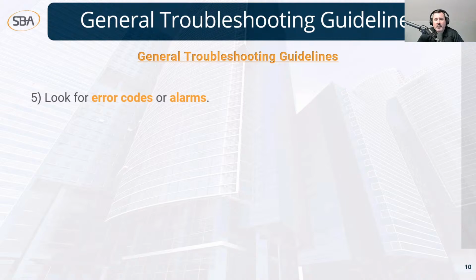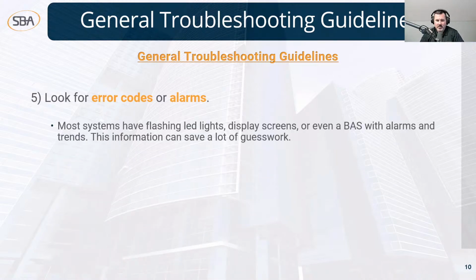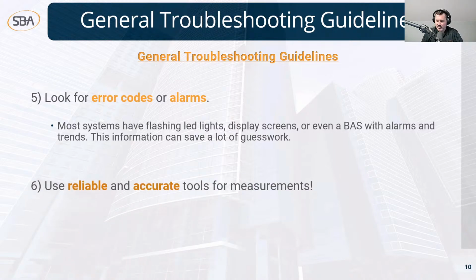Number 5, and this is a big one: look for error codes or alarms. I see this all the time. One of the first things people want to do if equipment's not working is kill power to it, but if you kill power, a lot of times you clear those error codes. Most equipment will at least have flashing LED lights, some have display screens you can toggle through, or if you're lucky, you'll have a BAS system with all the alarm data and trends of what was going on when the equipment went into alarm. That can save you a lot of guesswork because you get the big picture and it'll tell you exactly what the failure was.